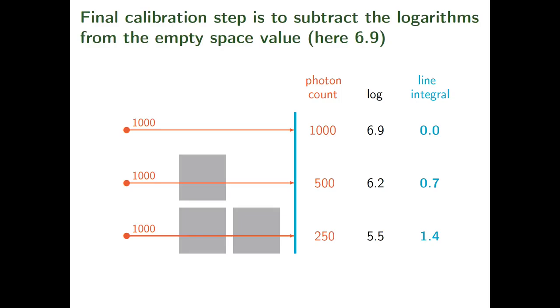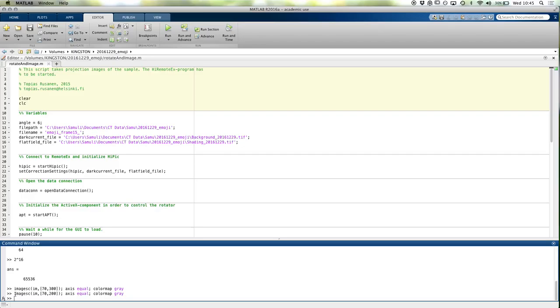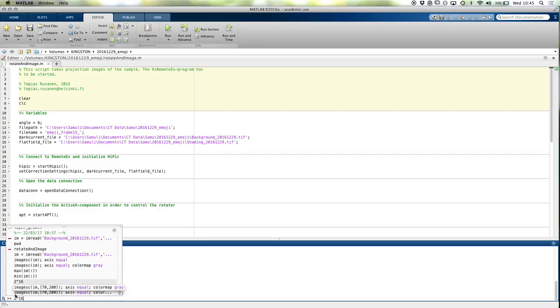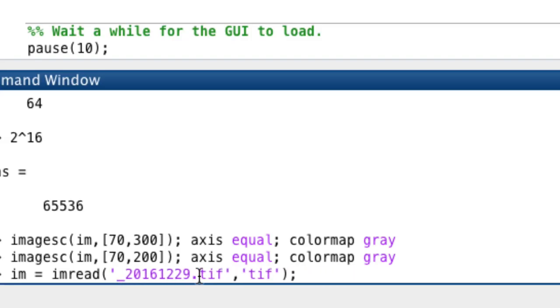In the simple ideal case we did the empty space measurement in one pixel and used the value for the other pixels, but this may not be a good idea because the pixels are not identical in practice. So we should actually measure the empty space for every pixel. In practice we first put nothing between the x-ray source and the detector and take empty images — that's what this shading image is. Let's take a look at that in MATLAB as well.